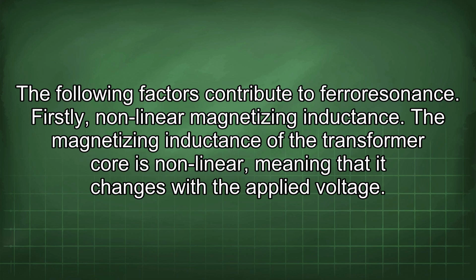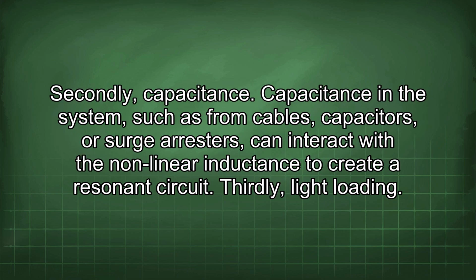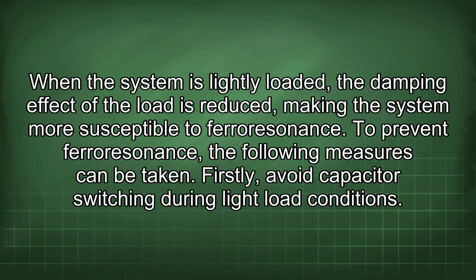Firstly, nonlinear magnetizing inductance. The magnetizing inductance of the transformer core is nonlinear, meaning that it changes with the applied voltage. Secondly, capacitance. Capacitance in the system, such as from cables, capacitors, or surge arresters, can interact with the nonlinear inductance to create a resonance circuit. Thirdly, light loading. When the system is lightly loaded, the damping effect of the load is reduced, making the system more susceptible to ferroresonance. To prevent ferroresonance, the following measures can be taken.